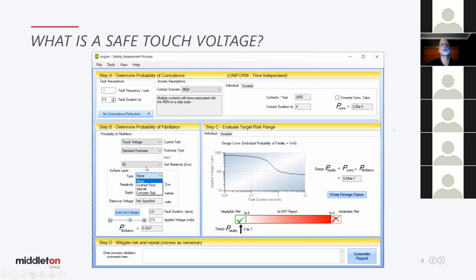We've got other inputs about soil resistivity. The higher the soil resistivity, the more insulation layers here. We've got surface layers. If you've got crushed rock or asphalt or concrete, this can increase the resistance of the circuit and therefore increase the allowable voltage for a given current that's deemed to be hazardous.